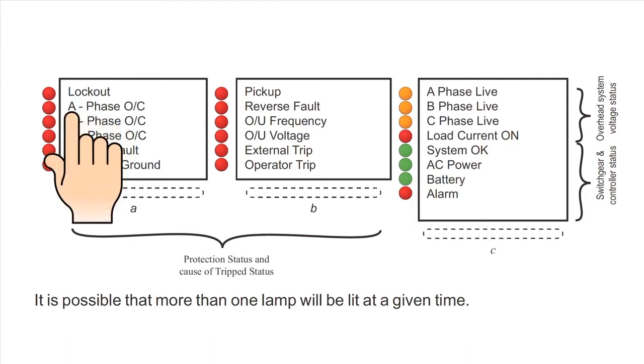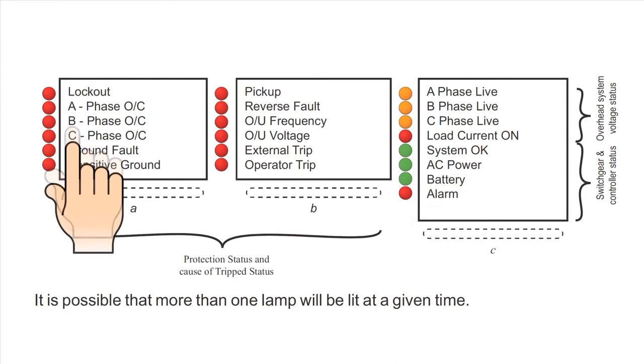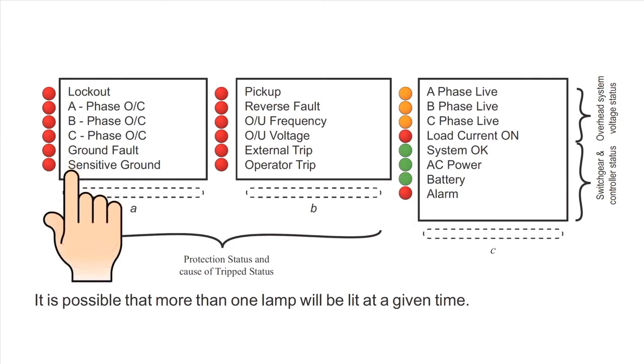A, B, and/or C phase over current. The most recent trip of the recloser was caused by an overcurrent event due to a fault on the relevant network phase or phases. These LEDs are red when activated. Ground fault. A ground fault has caused the recloser to trip. The LED is red when activated. Sensitive ground. The recloser has tripped due to a sensitive ground fault event. The LED is red when activated.